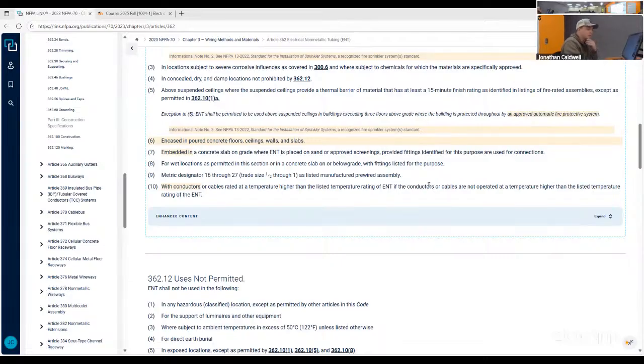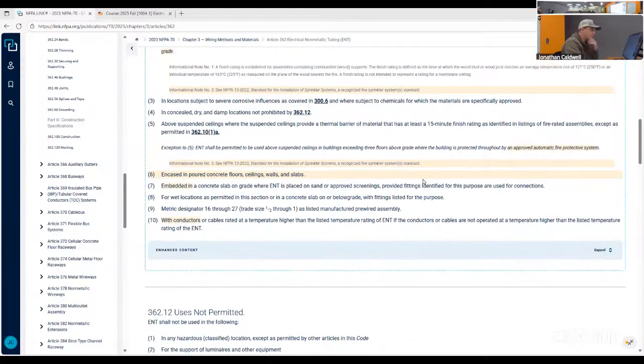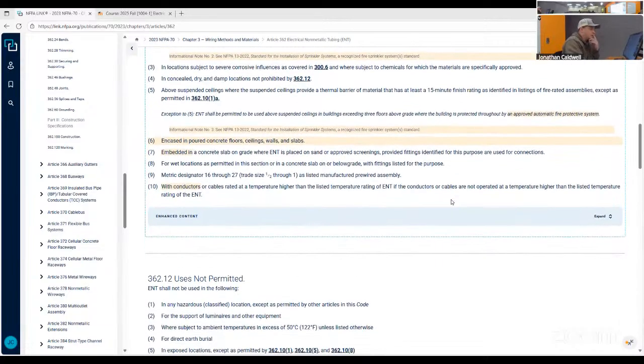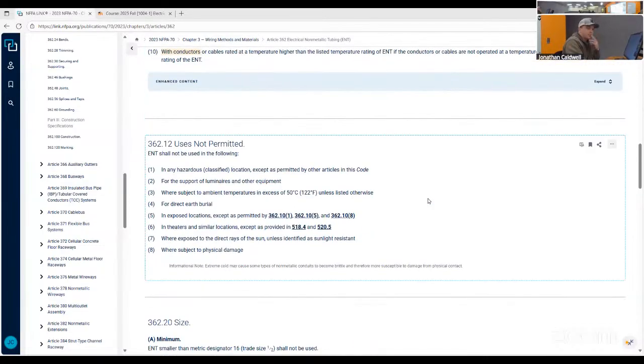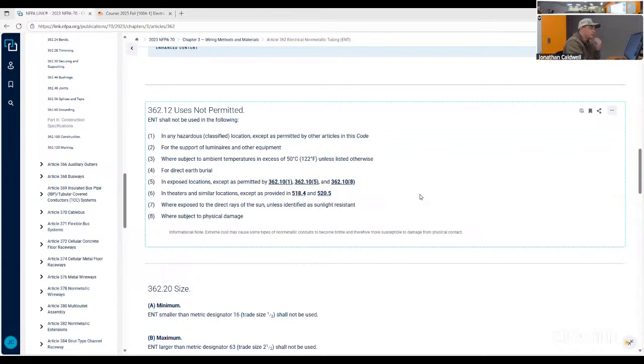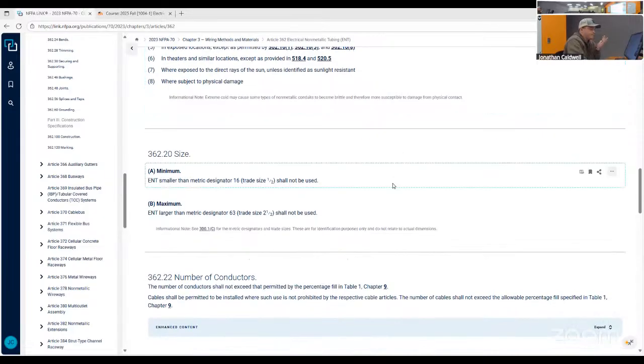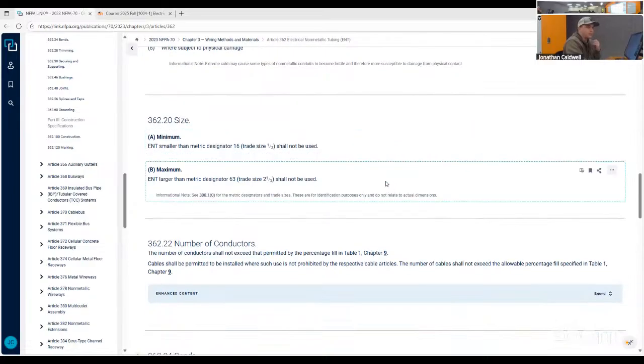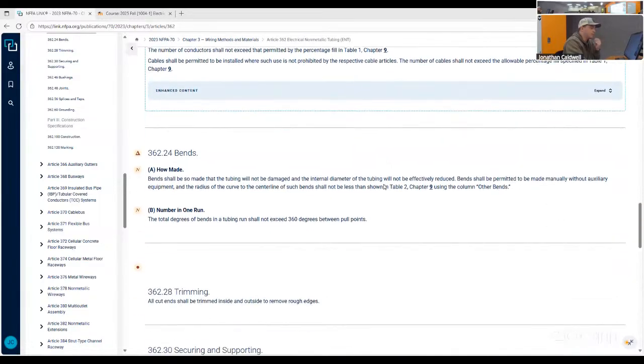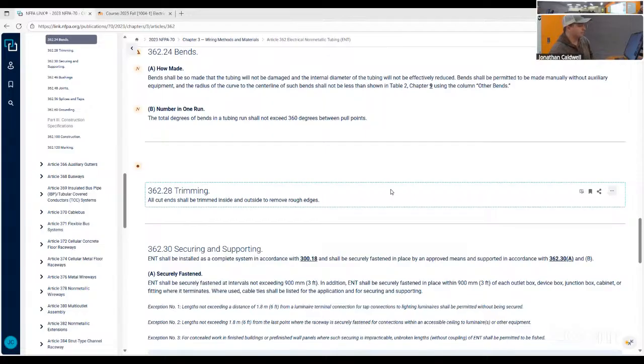So I'm sure you guys can think of other manufactured. But pretty much ENT just replaces Romex at the end of the day. Obviously there's some gray area that you go into with it. We've used it in commercial buildings before, just to make it cheaper for the customer, mainly for data drops and things like that, because that cable will never exceed that temperature rating, hopefully. But if it does, there's a serious issue. But that's pretty much where we use ENT, as our company does. You can use it a lot of different places.